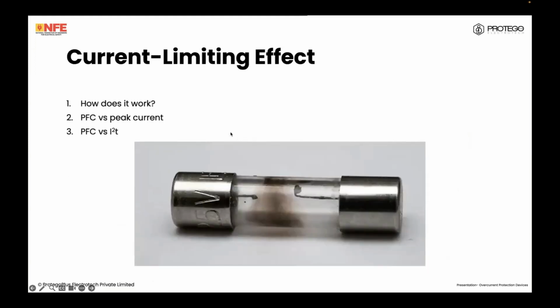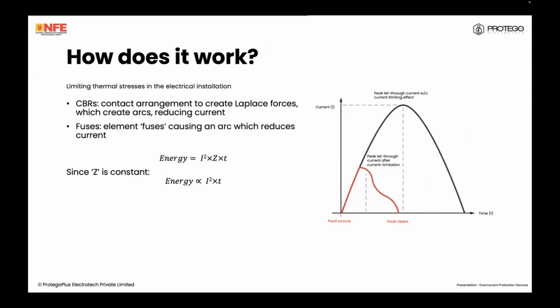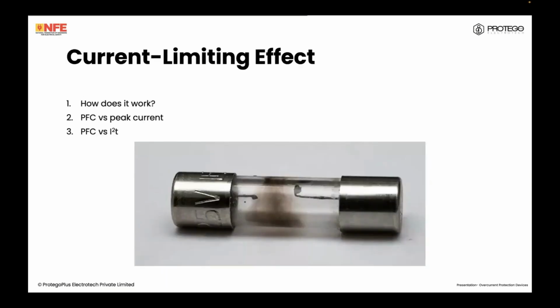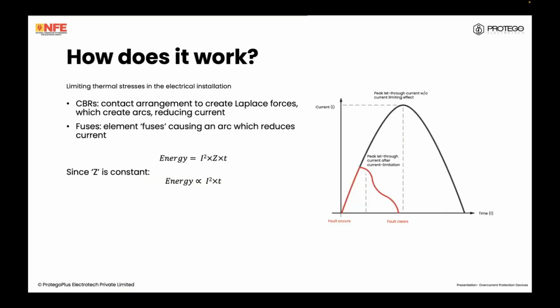Now, when it comes to current limiting effects, we'll look at how this works. How is the circuit able to limit current? How is this current limiting effect seen under prospective fault current versus peak current, which is let through in the first half cycle, and the prospective fault current versus the let through energy for these current limiting breakers or fuses? Fuses are often current limiting.